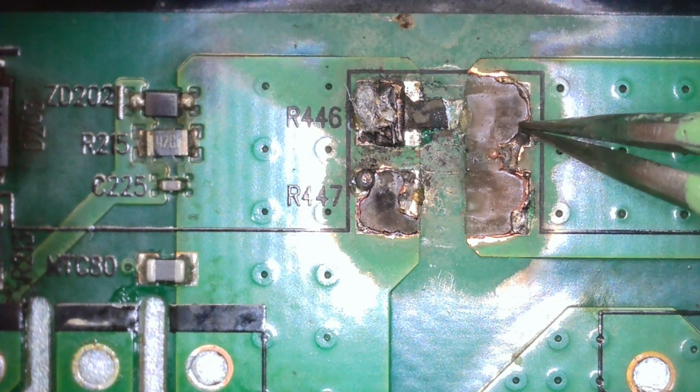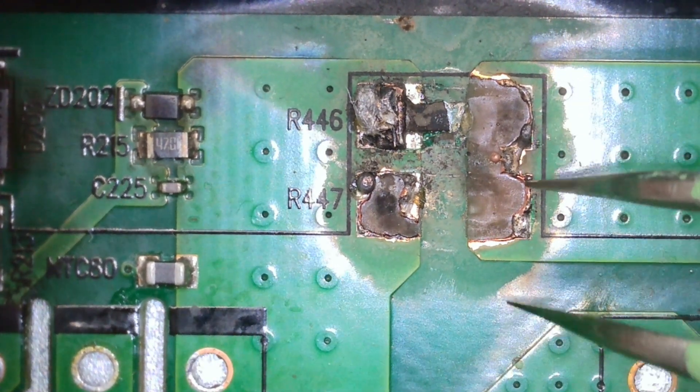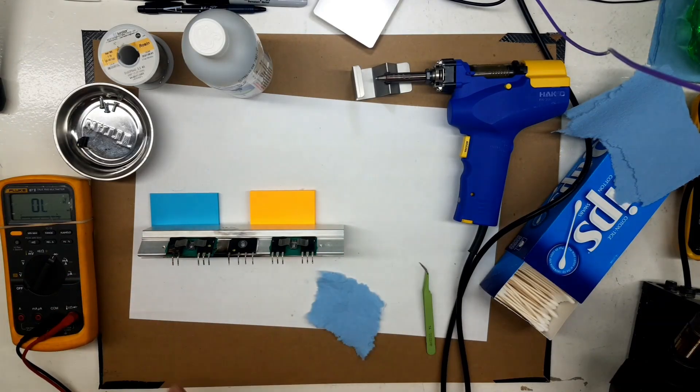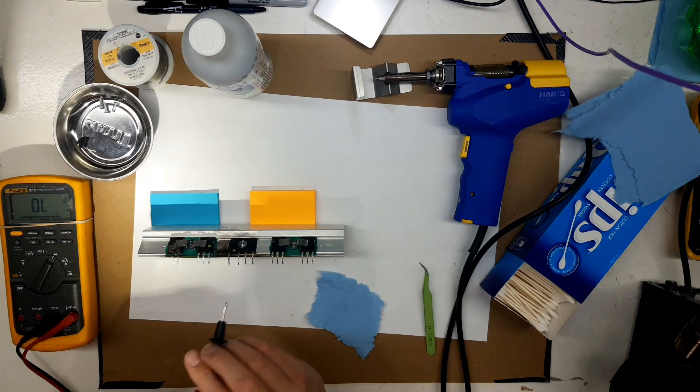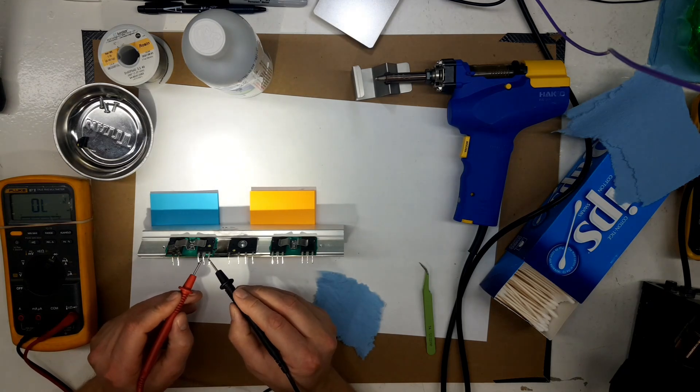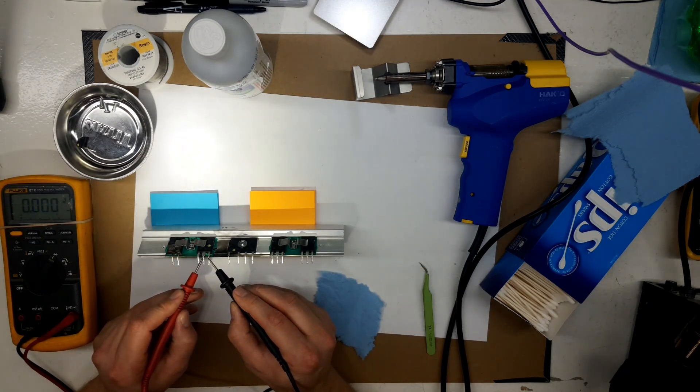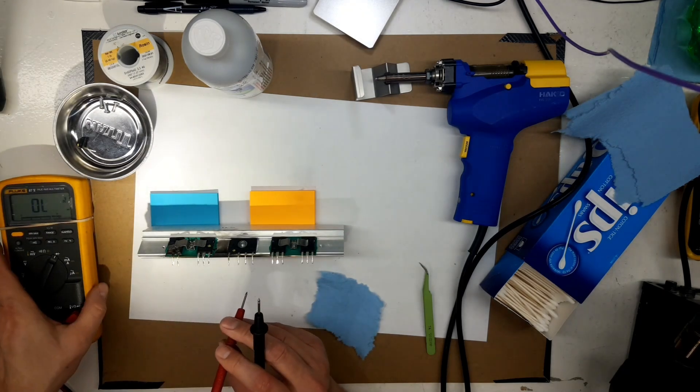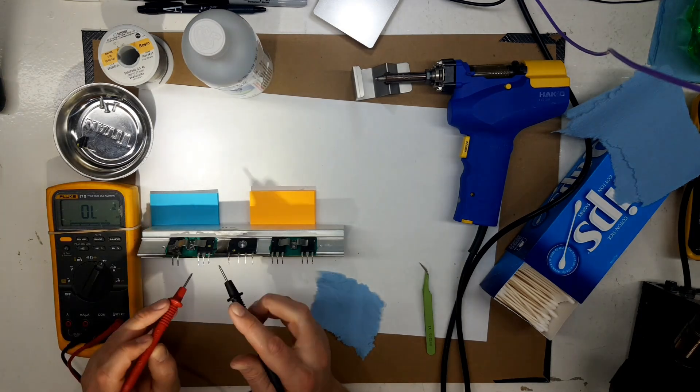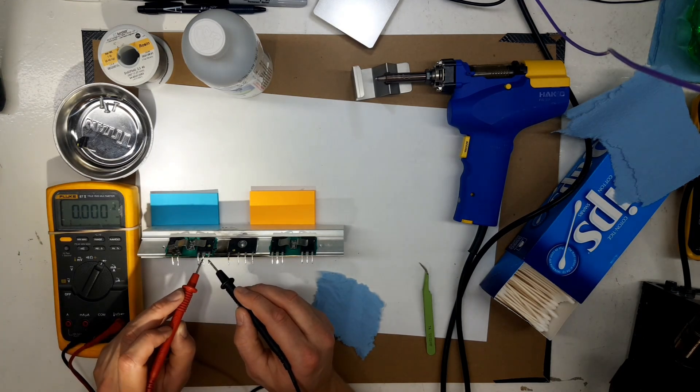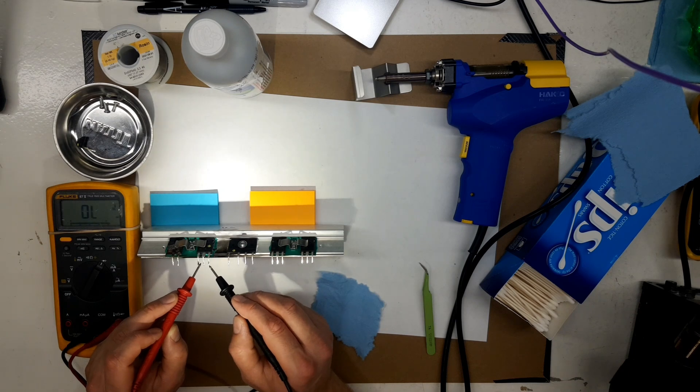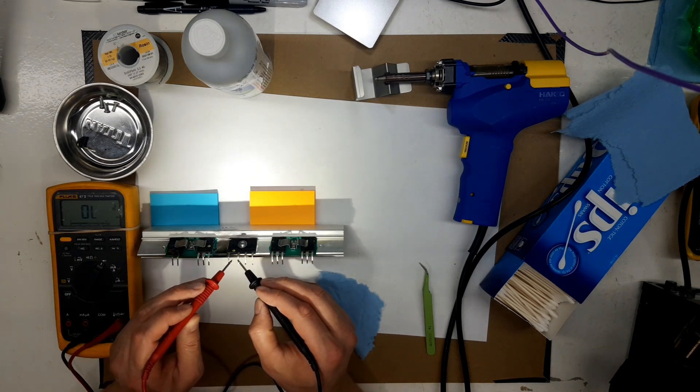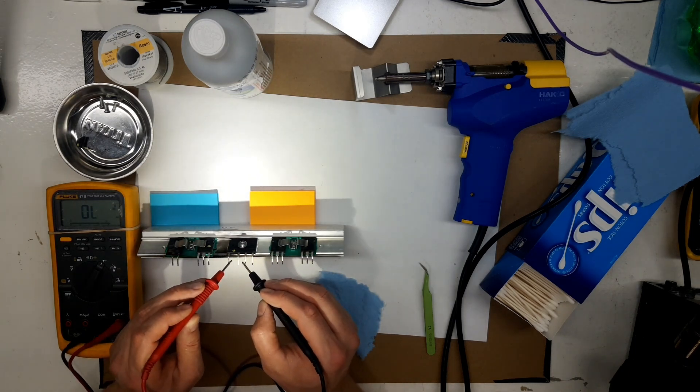There's the two main resistors I was telling you about that feed the power through to the inverter stage. So now we'll check the actual parts now that we're disconnected from the board. As you can see, the one IGBT on the left has got pieces missing. This one's completely shorted. Gate, collector, and emitter are all welded together. That usually happens when IGBTs blow. Either they end up like the one on the left or the one I'm testing now. And the bridge rectifier has some shorted diodes in it.